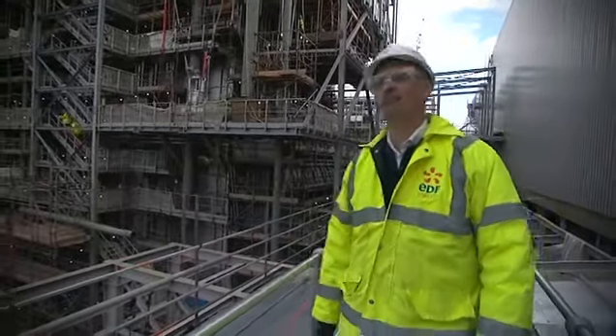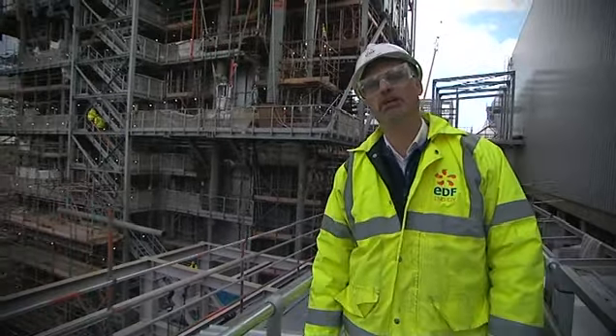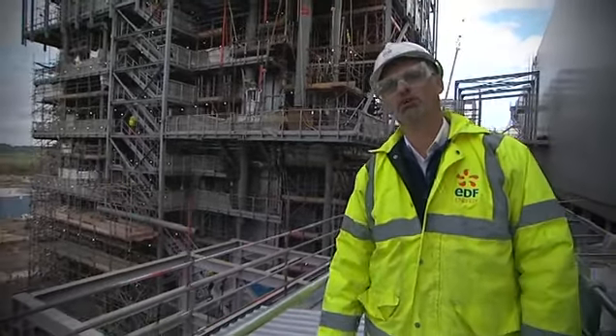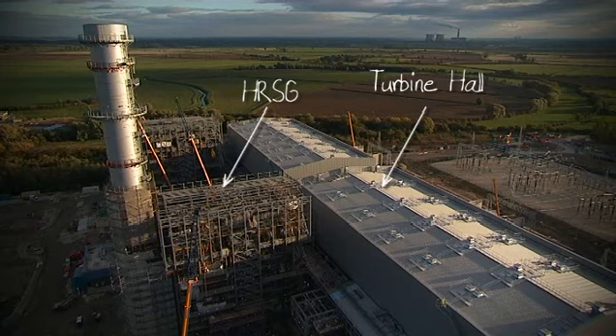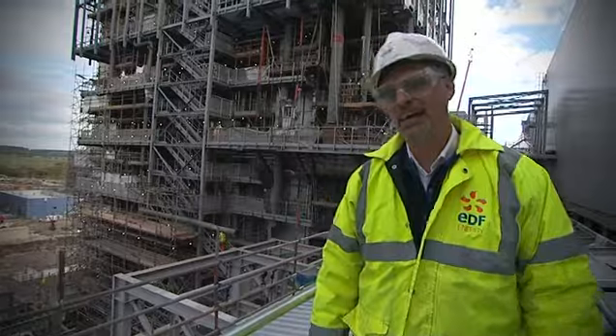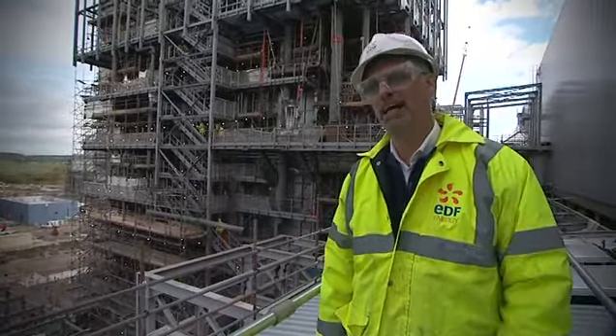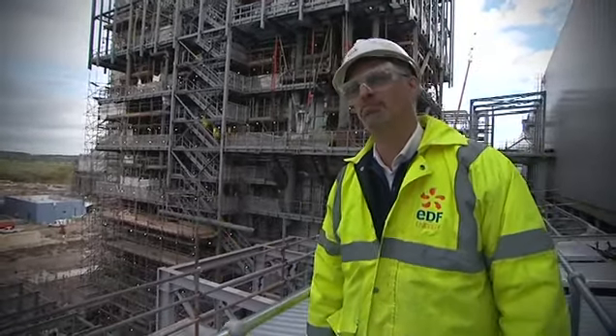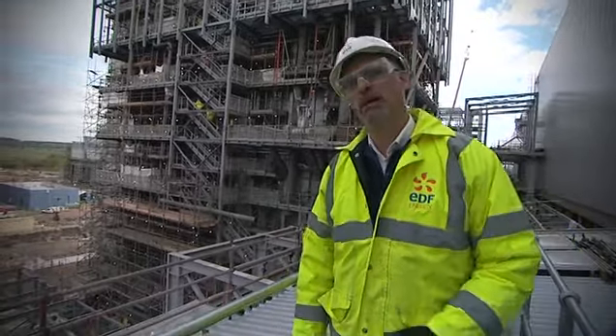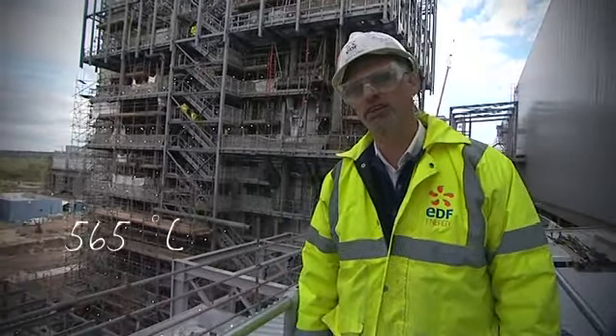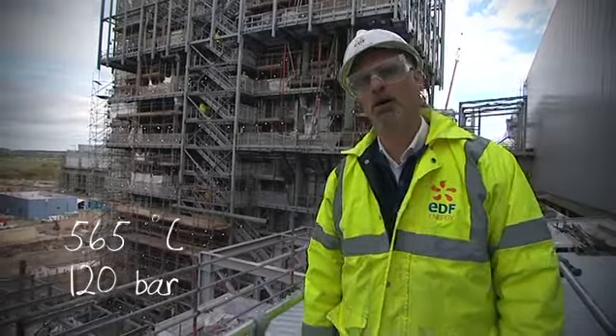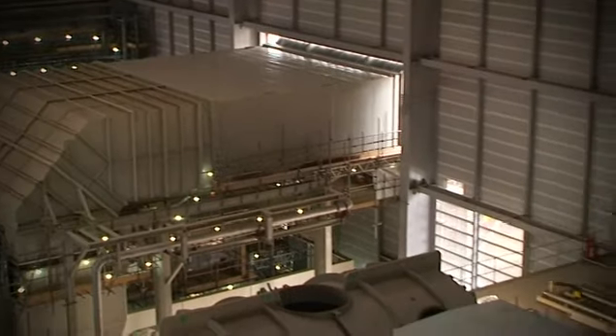This is the next phase in the process. This is the heat recovery steam generator, or HRSG for short. And this is what makes the CCGT process so efficient. It takes waste heat out of the gas turbine exhaust and uses that heat to convert water into steam. Once that steam has been heated to 565 degrees C and 120 bar pressure, it's conveyed onward to the steam turbine.